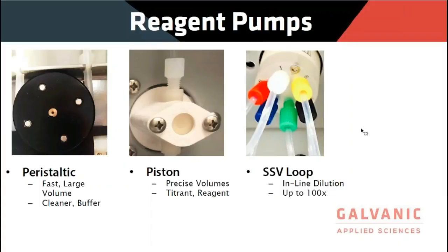Reagent pumps, we have 3 different ones that we use. We have a peristaltic pump that we use for fast, large volumes. So this could be a cleaning standard or a buffer solution. This is where we don't really need accuracy so much as fast volumes of a liquid. You can also use this for special applications where we need to do dilution by sucking out sample from the reaction cell. The piston pump is where we get our accuracy for very precise volumes. So this is where we're dosing titrants, color indicators, anything where we need great accuracy. And then we also have a small sample valve loop, the SSV, where we can do dilution up to 100 times and sometimes more. So for very high concentrations where a specific method is required, we tend to use this.